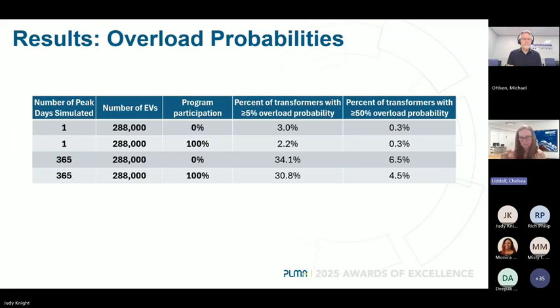So we started out doing these simulations for just 1 day, looking at the peak day of the year. But then we realized that we actually want to know the probability of transformer overload in a whole year. So we ended up modeling 365 days of doing 1,000 simulations for 288,000 EVs for the whole SMUD population of transformers. And then in that third column, you can see the percent of transformers with more than a 5% probability chance of overload without the program and with the program. So 0% program participation and 100% program participation.